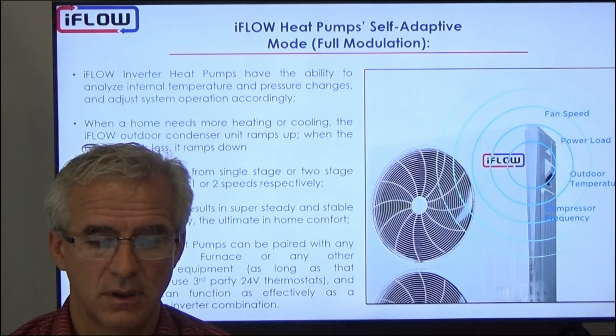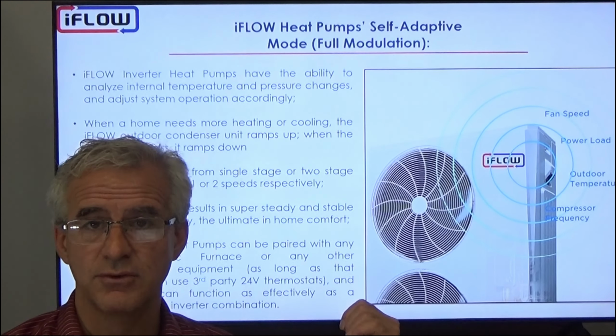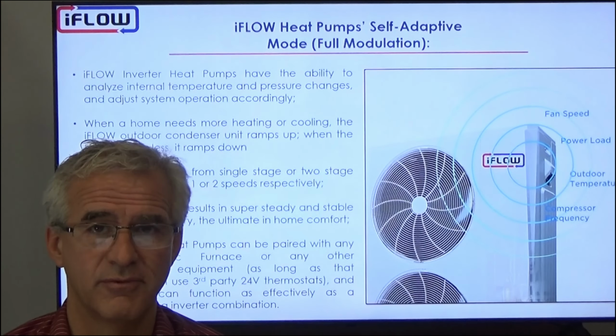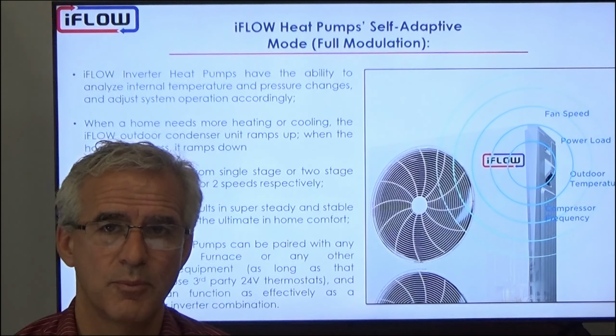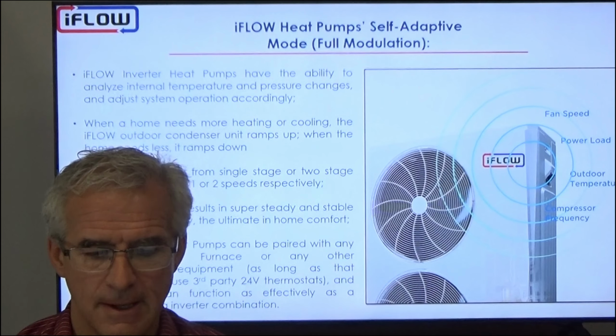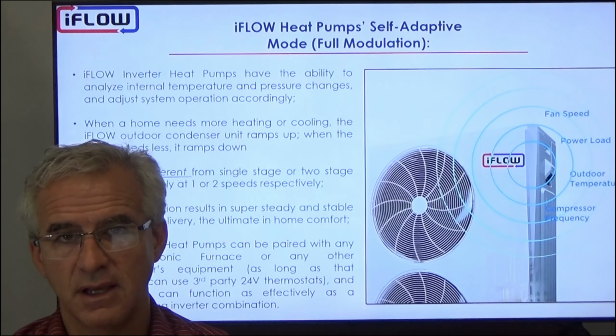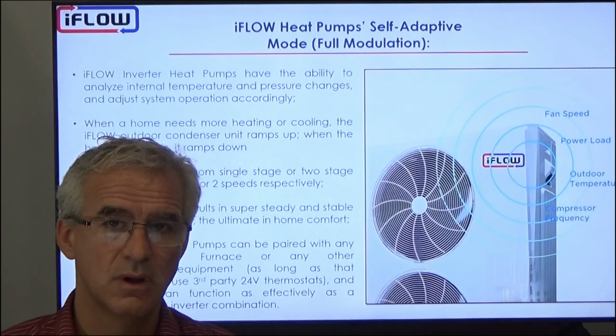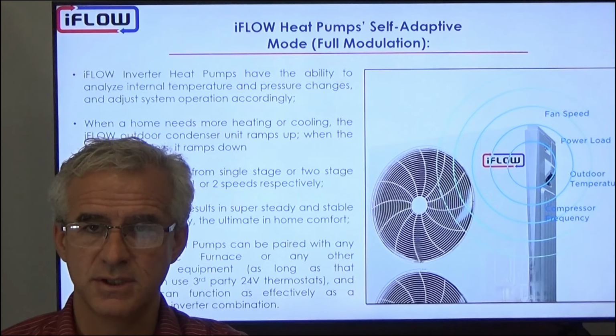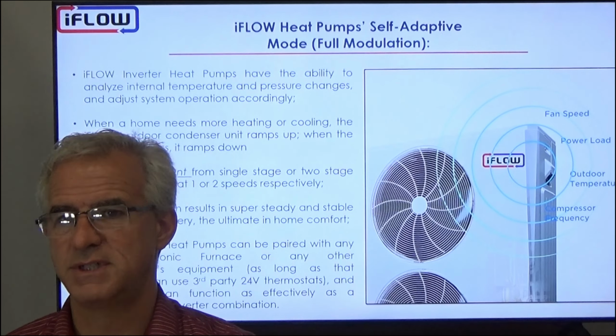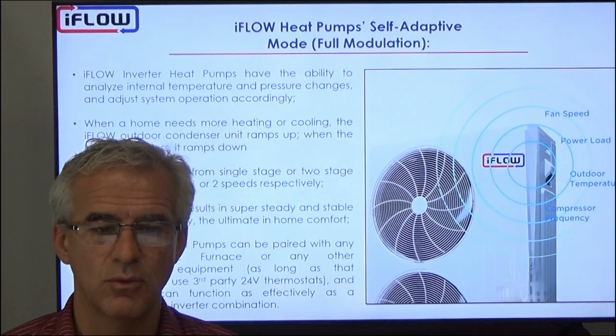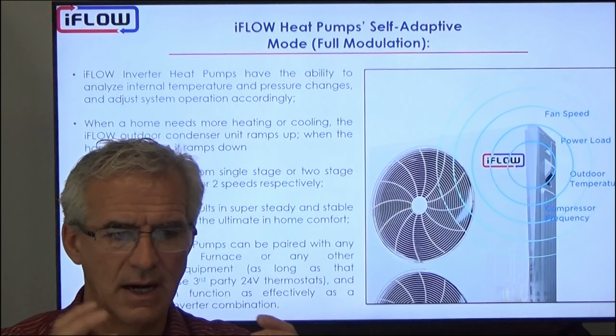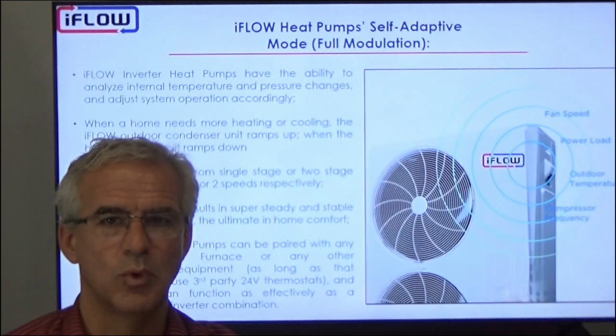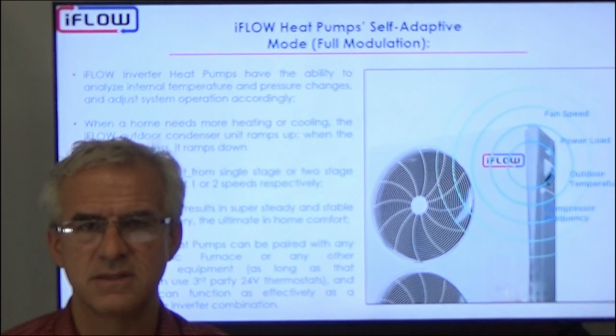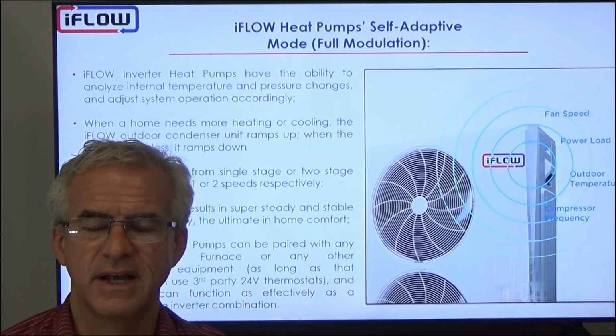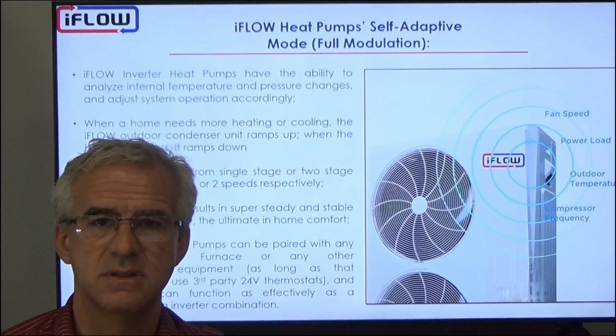The iFLOW inverter heat pumps can be paired with any iFLOW hydronic furnace, or any other manufacturer's equipment for that matter, as long as that equipment is able to operate with third-party 24-volt thermostats. Because of the ability of our inverter to modulate on its own, based on its own internal temperature and pressure changes, we don't need to communicate with any particular model. We don't require that you use our thermostat with our unit and our air handler because that's the only way the system will work. No, we have the flexibility to mix and match with any system out there.